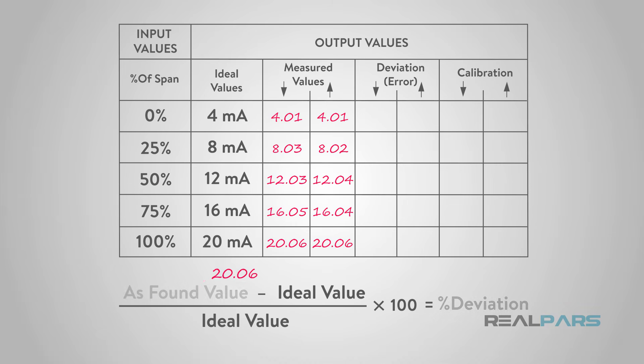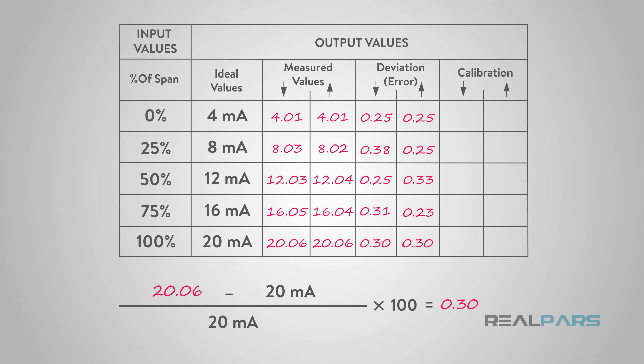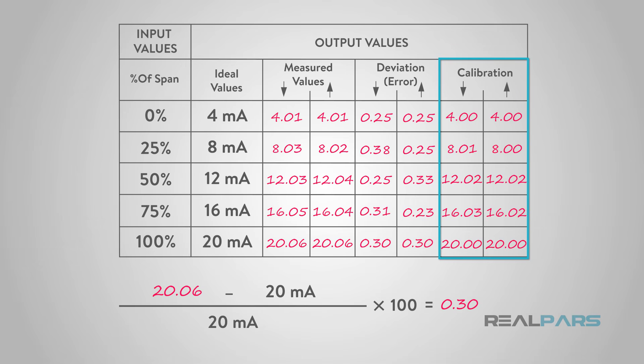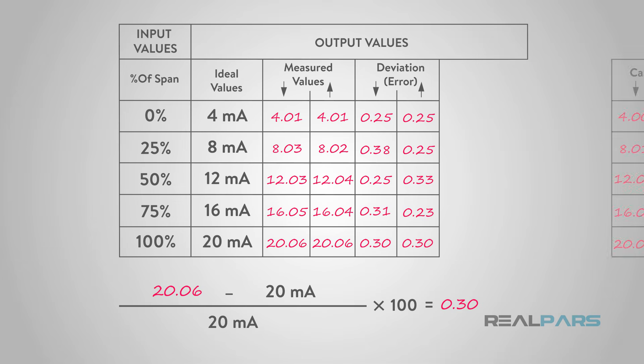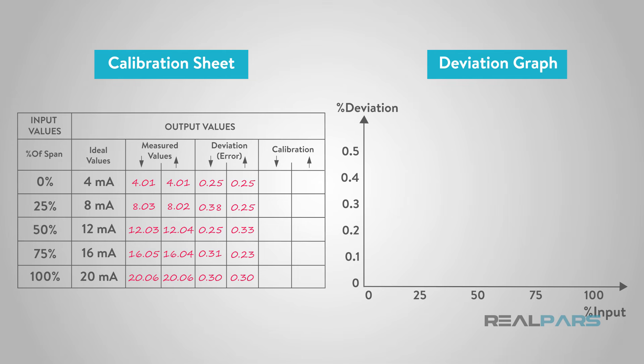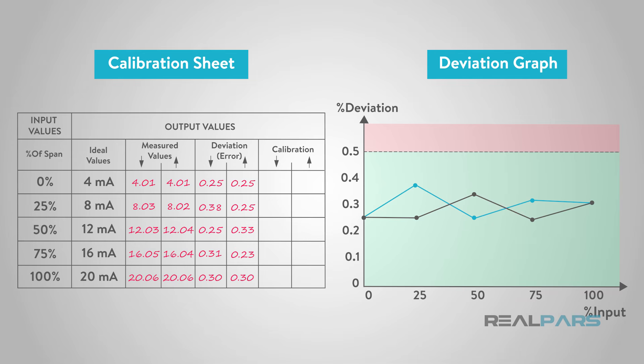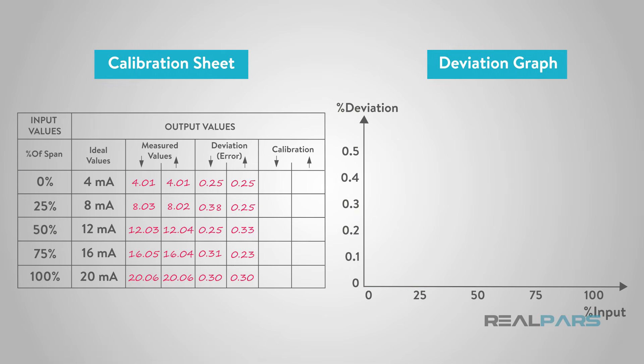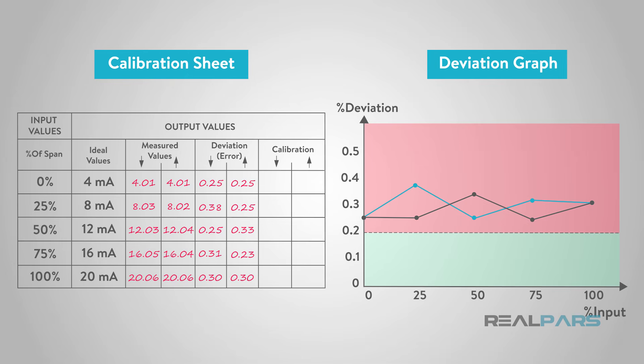The deviations at each checkpoint are calculated and compared to the deviation maximum allowed for the device. If the deviation is greater than the maximum allowed, then a full calibration is performed. If the deviation is less than the maximum allowed, then a sensor calibration is not required. For example, if the maximum deviation tolerance is 0.5%, we see from the graph that the deviations are all less than 0.5%, so no additional calibration is required. But if the maximum deviation tolerance is 0.2%, and some deviations exceed that, then a sensor calibration is required.